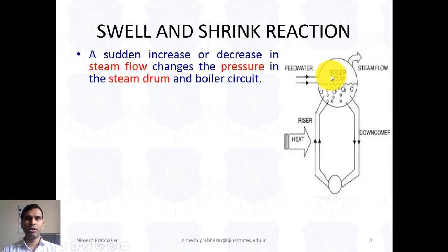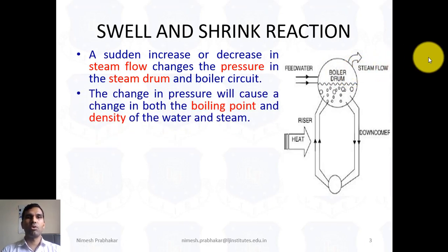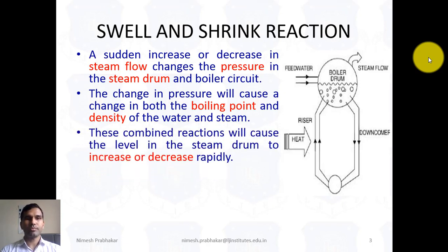Due to this increase or decrease in pressure, the swelling and shrinking effect occurs. The change in pressure will cause a change in both the boiling point and the density of the water and steam. This combined reaction will cause the level in the steam drum to increase or decrease rapidly.